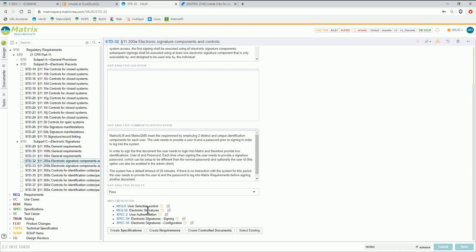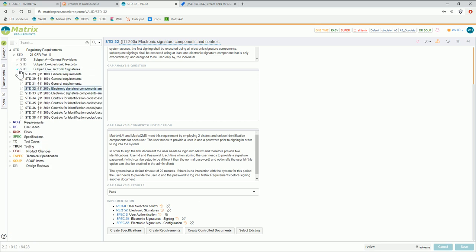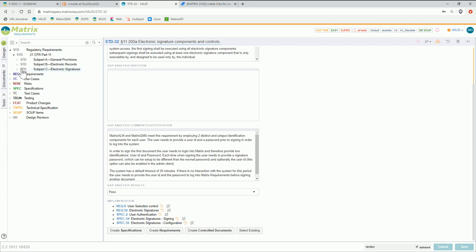Then we actually link directly from that regulatory requirement to a different level — it can go to top-level marketing or user requirements, or to lower-level system requirements or software requirements, or if you want you can also link directly to tests. It depends on what the requirements are. This works very well for requirements which are really for your product, such as parts of IEC 60601-1 or IEC 60601-1-8 for alarms which impact your product. But sometimes you have requirements from standards which are not really related to your product — for example, everything about processes like ISO 13485 doesn't really belong here because it has no direct impact on one requirement or specification.